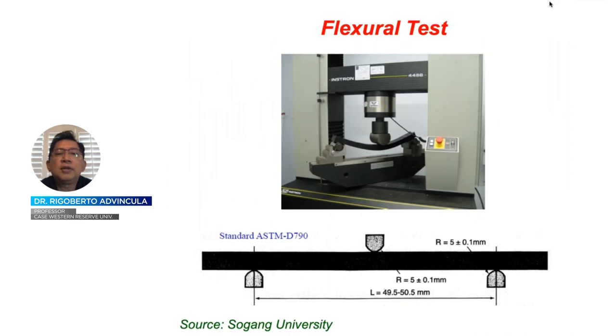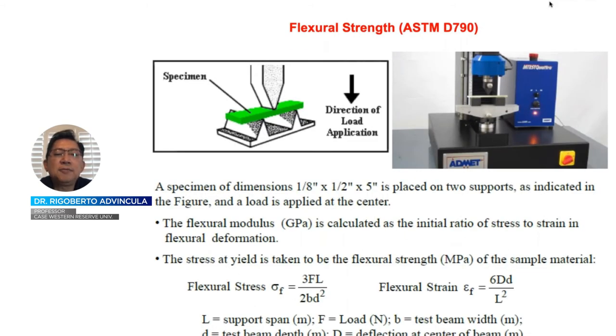Moving to three-point bending or flexural strength: the ability to bend a material does not mean it is elastomeric but simply a deformation allowed without breaking or snapping the material, which has importance in terms of ultimate strength. Using ASTM D790, a three-point bending test with specified dimensions and distance, one can get the flexural strength or modulus of a material in megapascals.